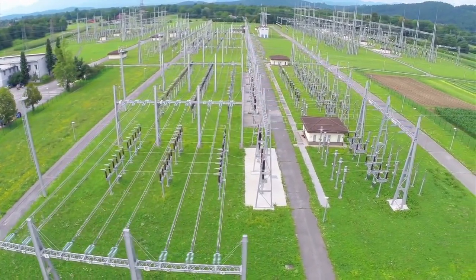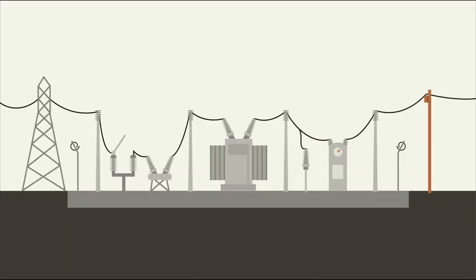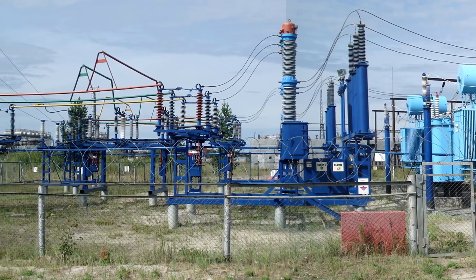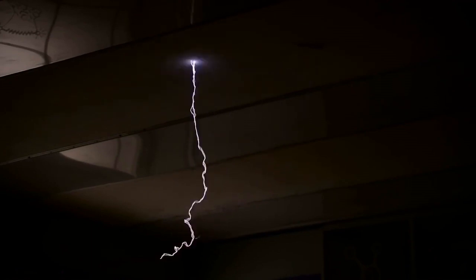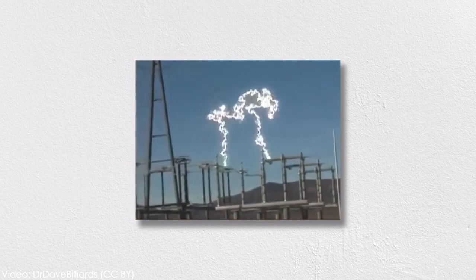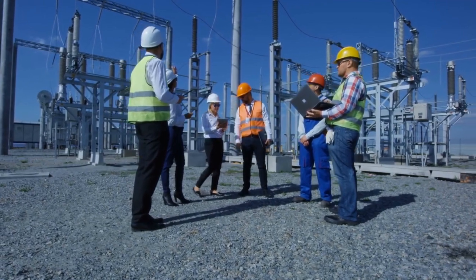The arrangement of the bus is a critical part of the design of any substation because it can have a major impact on overall reliability. Like all equipment, substations occasionally have malfunctions or things that simply require regular maintenance. To avoid shutting down the entire substation, we need switches that can isolate equipment, transfer load, and control the flow of electricity along the bus. Turning on and off high voltage lines isn't as simple as flipping a light switch — at high voltages, even air can act like a conductor, meaning even if you create a break in the line, electricity can continue flowing in a phenomenon known as an arc. Arcing is incredibly dangerous and damaging to equipment.